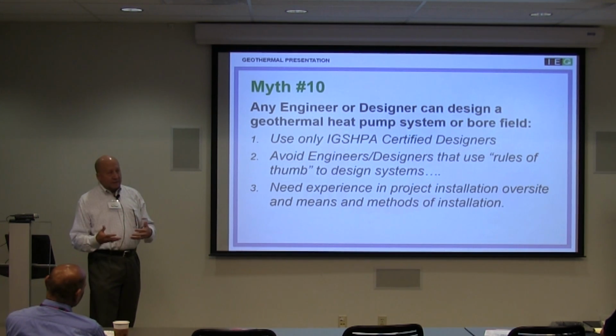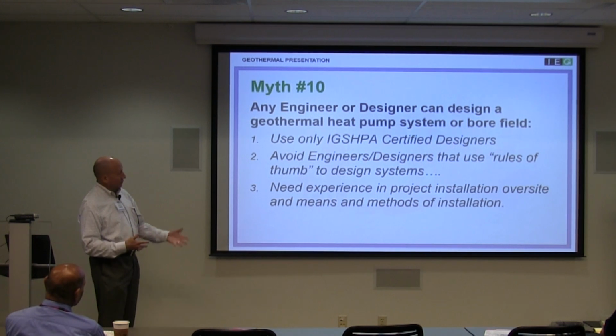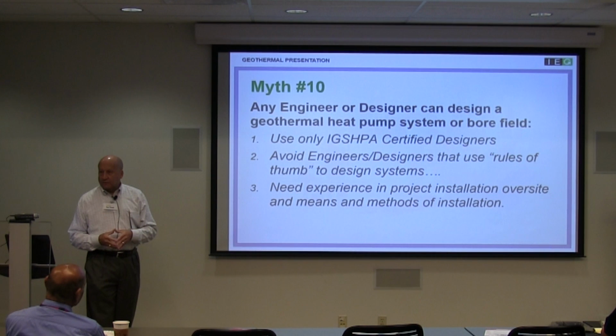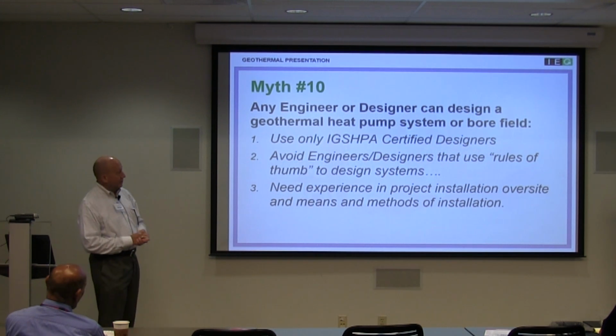Designing a geothermal system, the borefield side of it, reminds me of the days when we used to do thermal storage systems. You've got to look, you're talking ton hours, you're talking duration of heat load or heat gain or heat loss out of a building, and you've got to equate those.